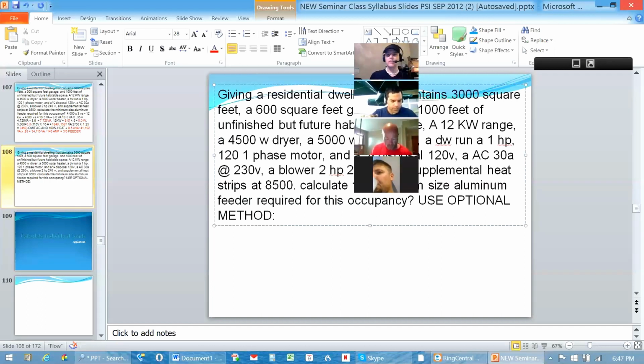If you look at B, then B is really the optional method, and that's the mechanics of it, and it's real simple. In step 1, they give you a list of all of the areas, just like under the standard method, where we started. They tell you what to include and what not to include, and how much to include for each one of those square feet in the same little paragraph. So B1 tells you to take the square footage minus any garage or open porches or unused, unfinished space not adaptable for future use. And at the very beginning it tells you that 3 volt-amps will be included for each one of those. So the beginning starts are going to be almost identical.